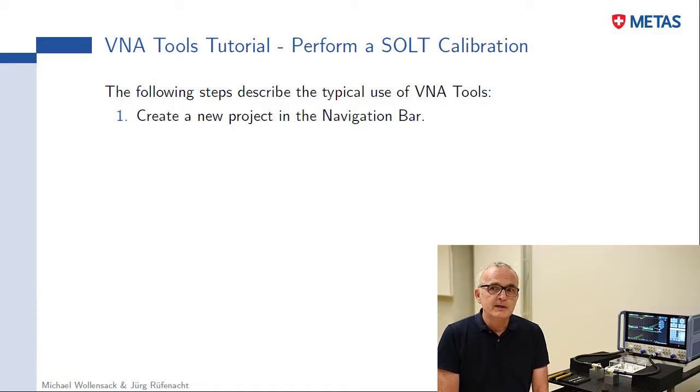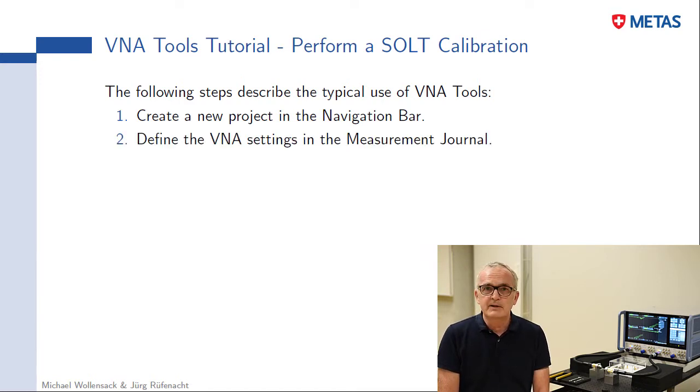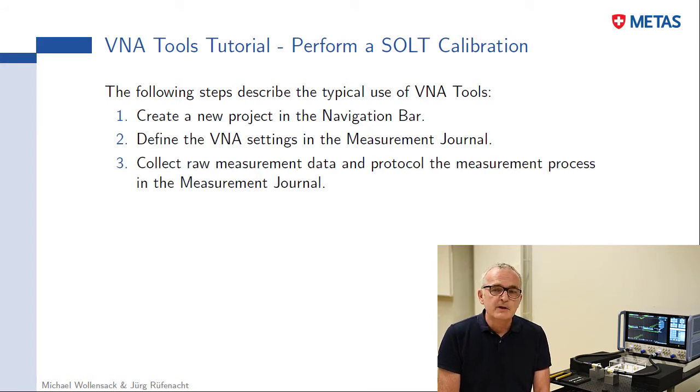First step, create a new measurement project in the navigation bar. Second step, define the VNA settings in the measurement journal. Third step, collect all raw measurement and protocol the measurement process in the measurement journal.